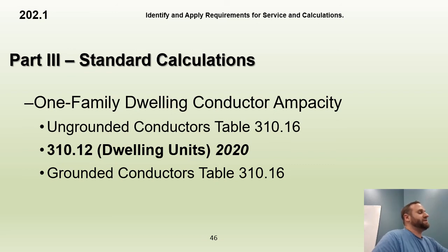In class, I said as long as it's 83%, I'm good to go. Doesn't matter. At no given point am I to install a conductor that has an ampacity less than the load calculated to be applied to it. And if we look up 1-aught, it's only good up to 150 amps.